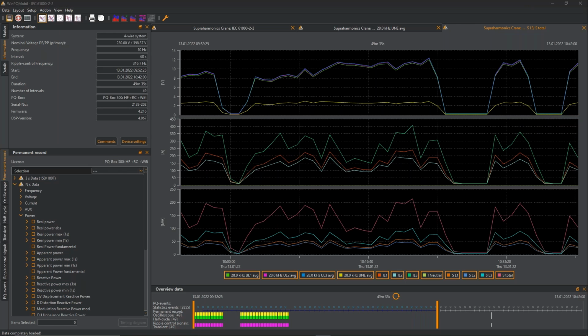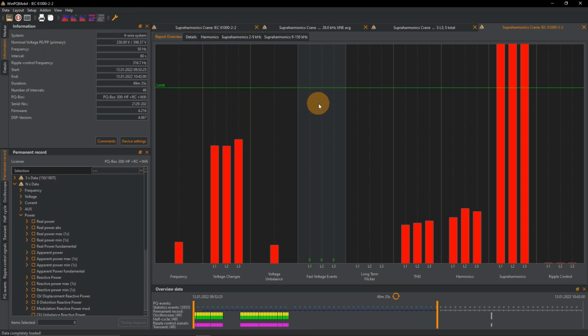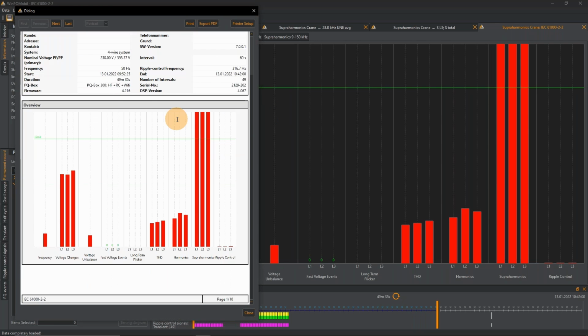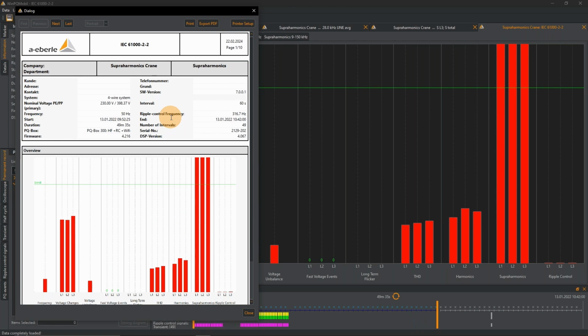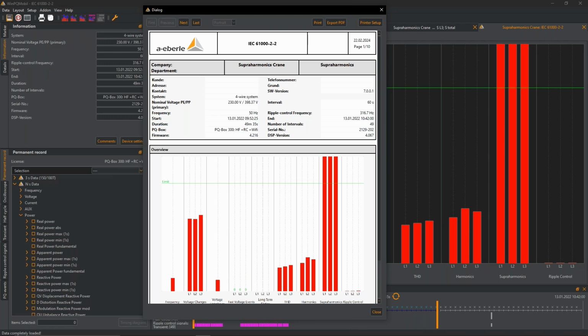So now I know the cause, and now let's evaluate the supraharmonics. Limit values are useful, and I selected for evaluation, for example, the IEC 61000-2-2. So now I could print out the settings, export in PDF, and hand it out to the customer, who in turn shows it to the crane manufacturer. Well, that's what we did. And the crane manufacturer said, okay, I was looking at the results, but you are evaluating according to the wrong standard. And he is right, unfortunately.